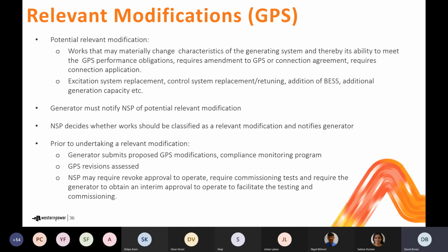Once that assessment is made, that places certain obligations on the generator that they need to meet before the relevant modification is undertaken. They need to submit any proposed GPS modifications, and any proposed modifications to the generator compliance monitoring program. Those modifications are then assessed in much the same way as you would assess an application to create a generator performance standard in the first place, so you go through the same assessment process that's in the technical rules. Out of that, you reach a stage where there's an agreement as to the new GPS and the new compliance monitoring framework.